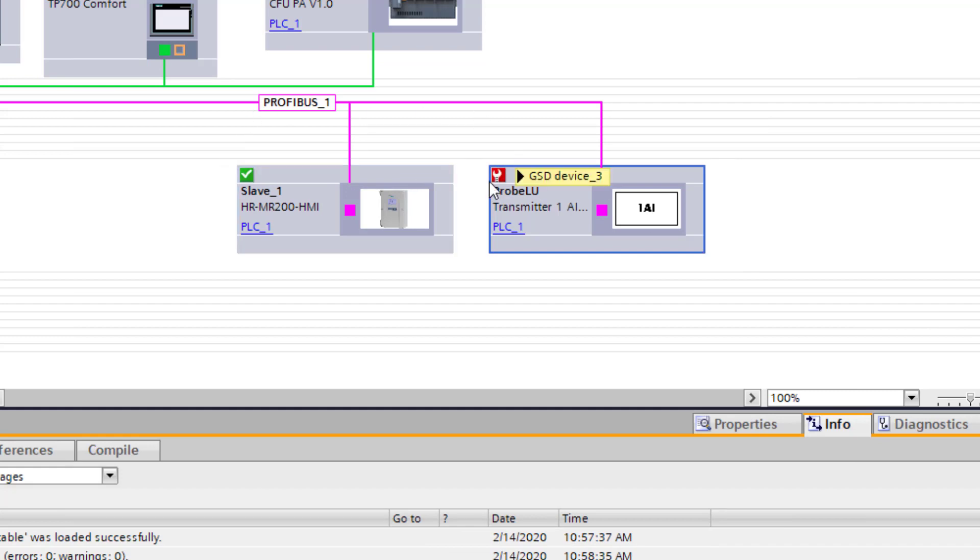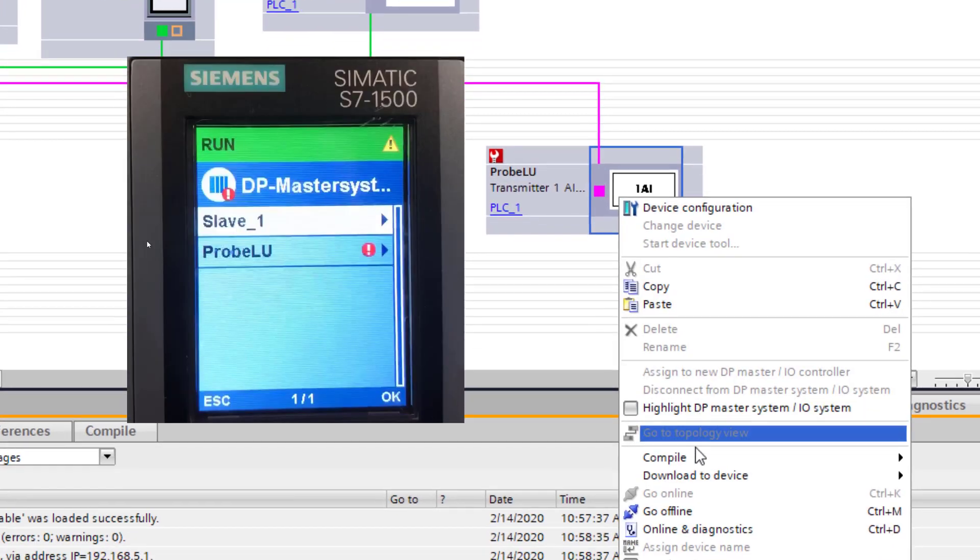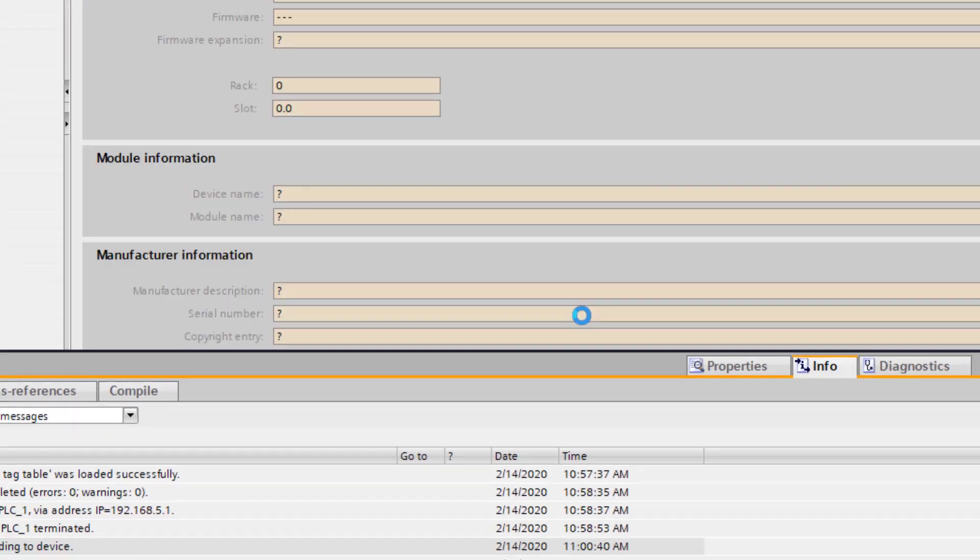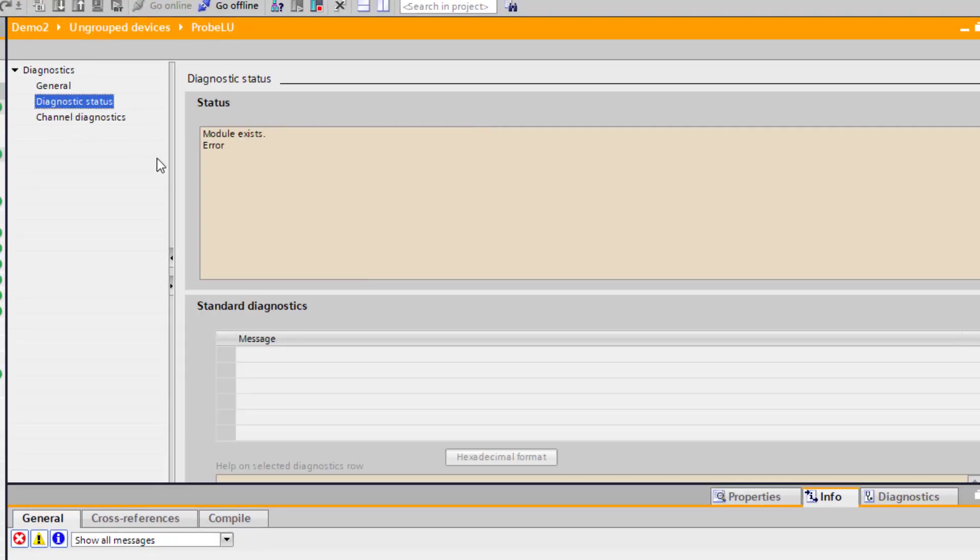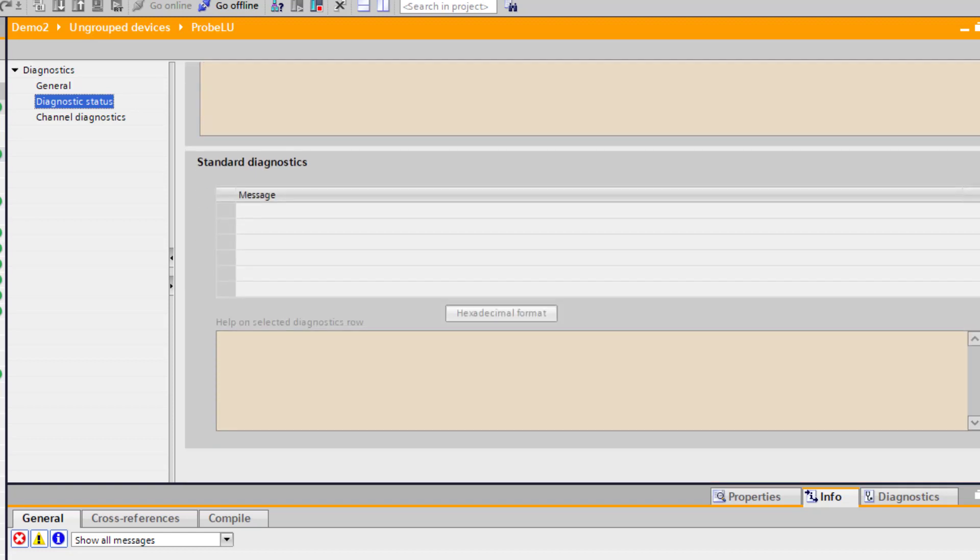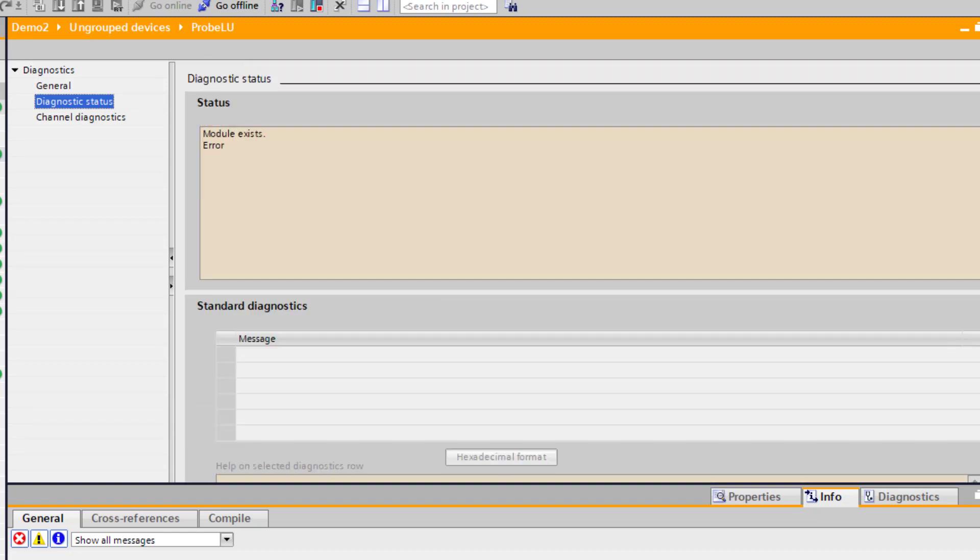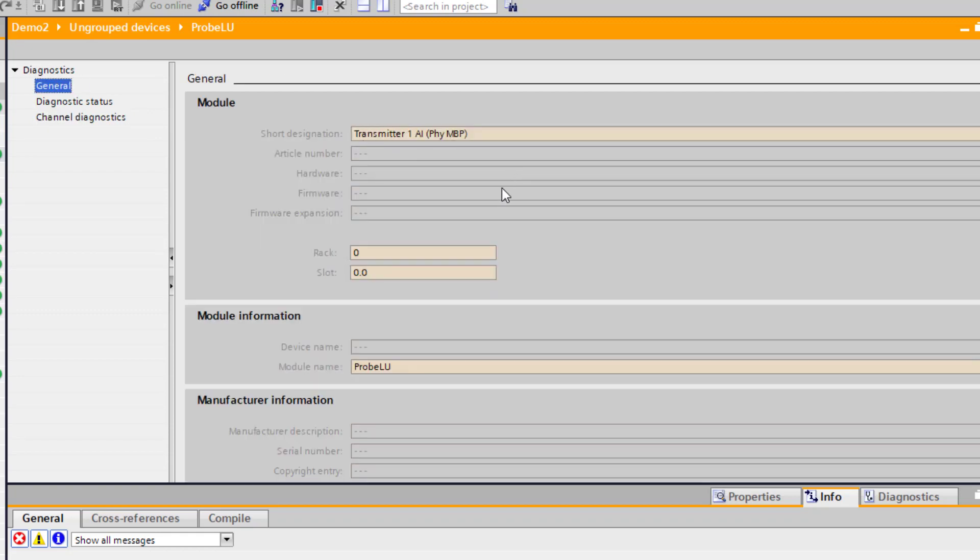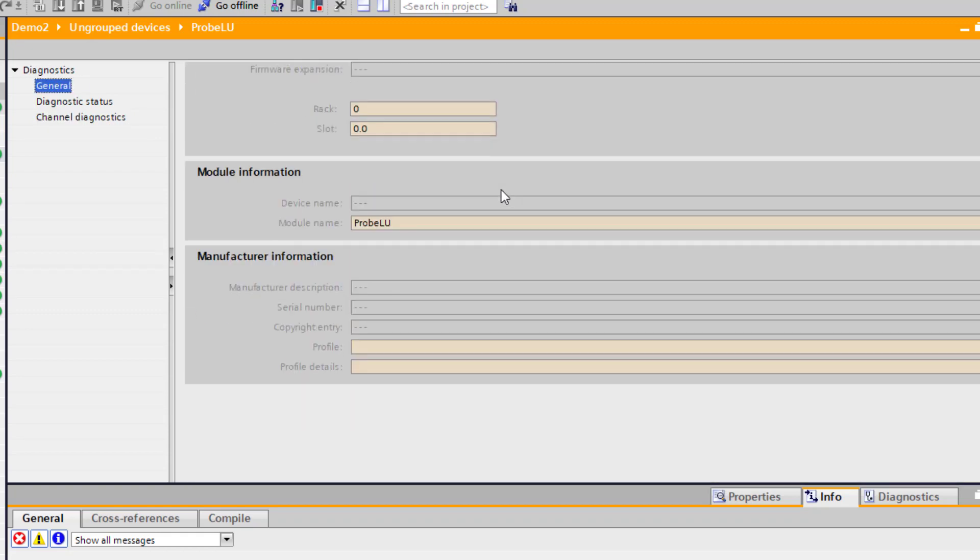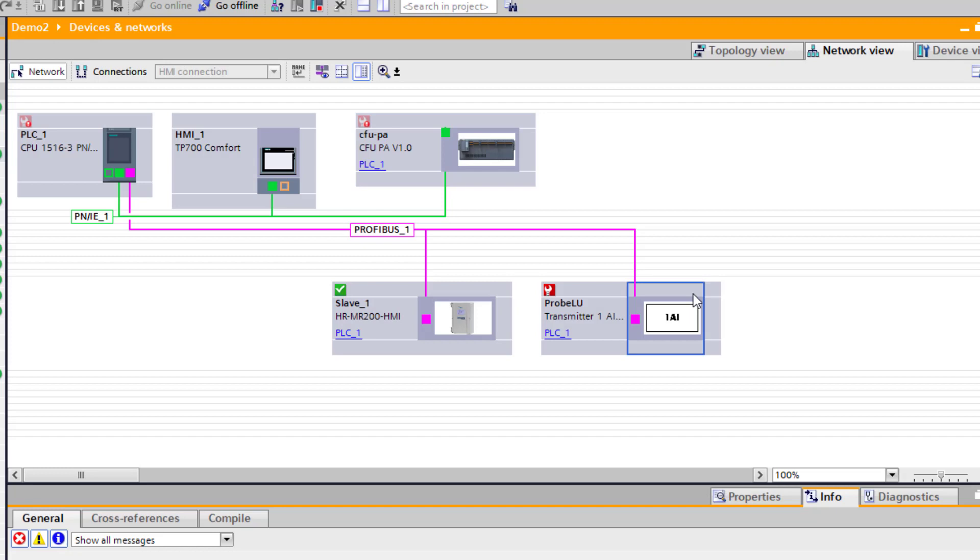And we're online. The instrument itself is in fault. Check the online diagnostics. Module exists. Error, and that's really about as far as TIA portal can go with determining the error. But we can see the error is with the instrument, so we need to see if we can add that to our PDM project and see what's wrong with it.